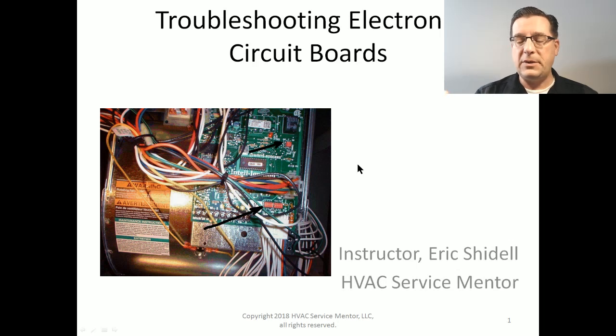And another more specific reason why is, say you've identified, if you're an electronics genius and you're able to identify that a specific component on the control board has failed, and you're going to replace it. Much of the time, the reasons for control board failure aren't because this particular component had a problem. It is often more because the entire control board or the entire circuit that component is in has experienced a problem. And all of the other components that are in that circuit or a part of that control board have experienced the same problem, which means they could be weak or show hidden damage, and it just doesn't make sense to only replace one component. We replace the whole thing. Okay, moving on.